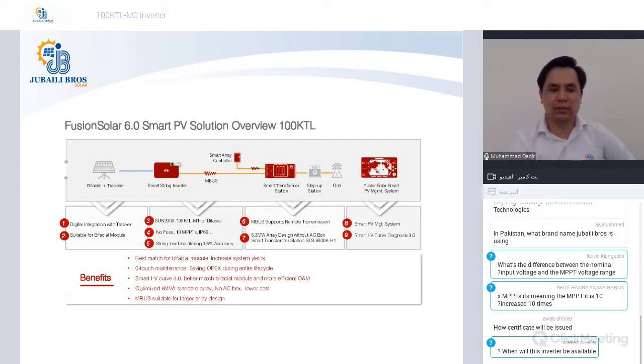So this inverter is zero-touch maintenance. This reduces the operational costs. The Smart IV Curve Diagnosis 3, which I will also be speaking about in my later slides, gives you an efficient O&M methodology and reduces time going to the field. You can sit at your desk and know which part of your PV plant is healthy, and if there are unhealthy strings in your PV plant, what needs to be done in order to mitigate that. So the Smart IV Curve Diagnosis is much faster compared to the previous versions.